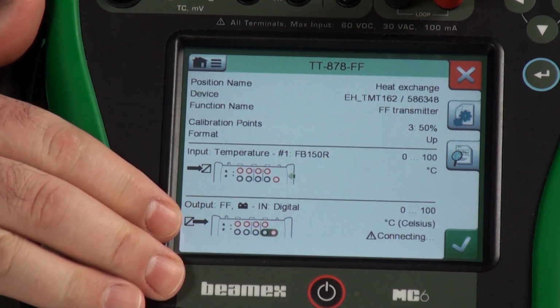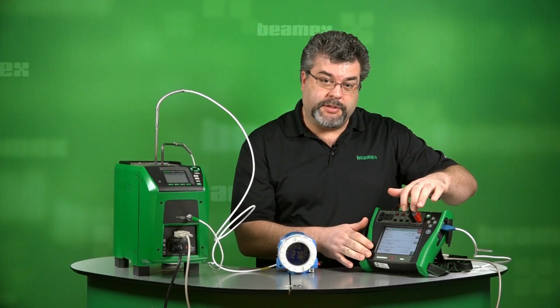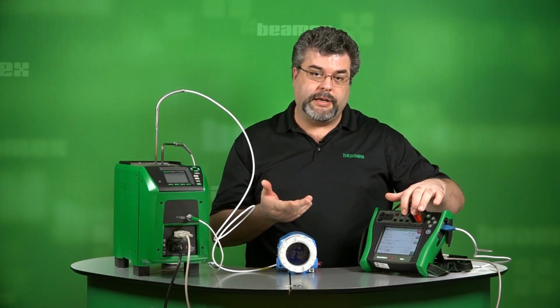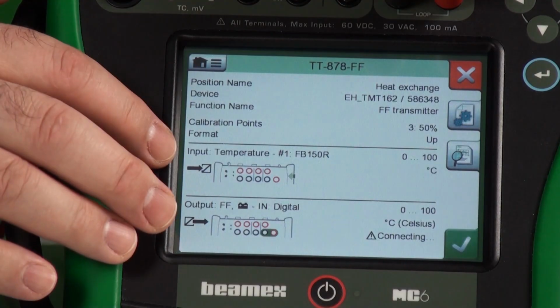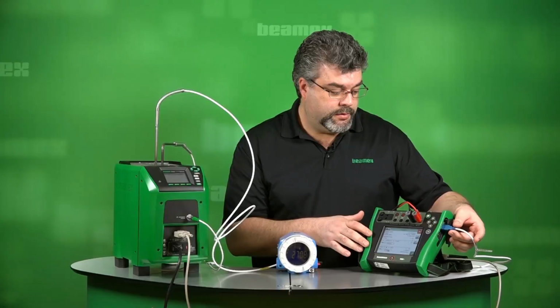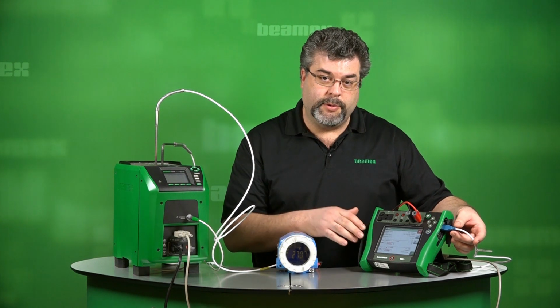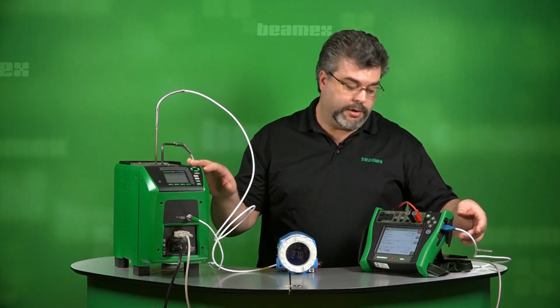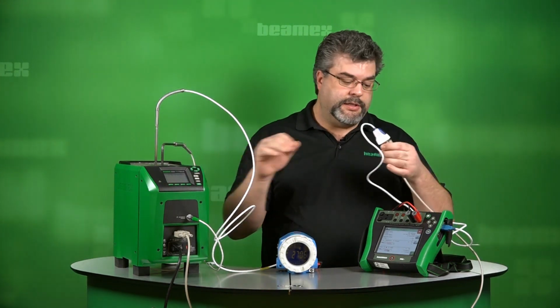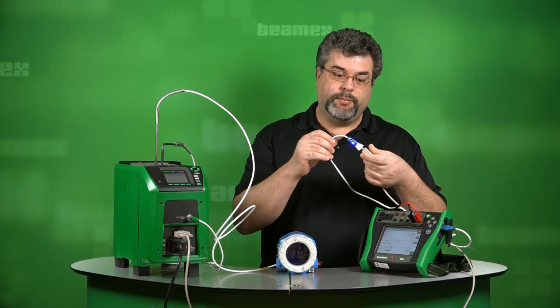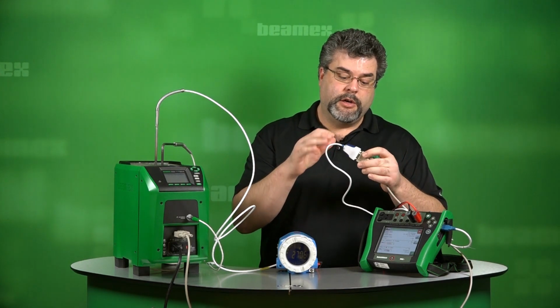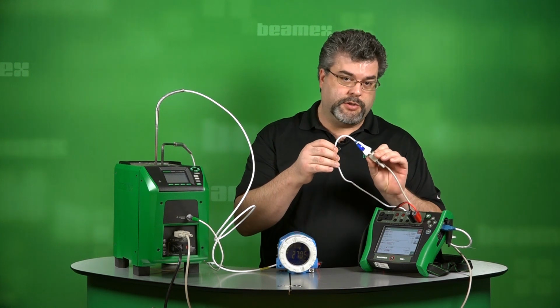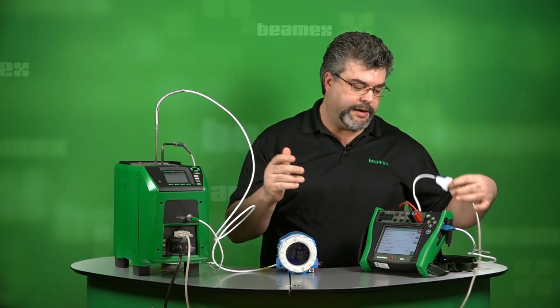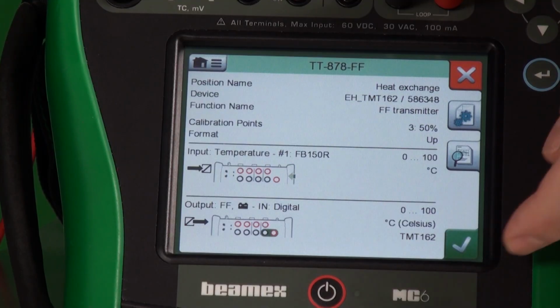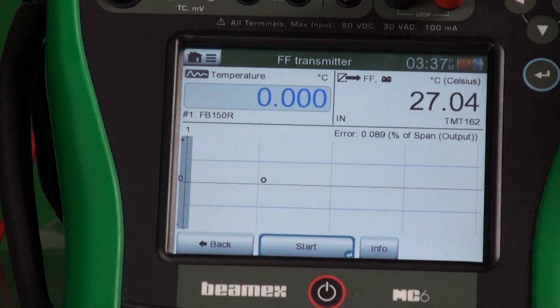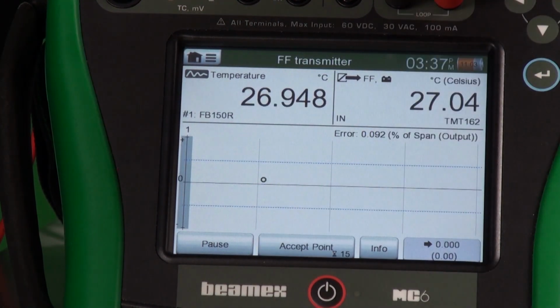So on the very bottom we can see that we'll connect the Fieldbus signal right here, and that's also where we'll get our loop power. And it's showing us that for our input, we're connected here via USB, and that's connecting over to our dry block. And we can see the communication happening with our USB to serial converter. One light is to transmit and the other one is to receive, so that's how it's talking right now. Press a check mark to get started, and then we simply hit start.